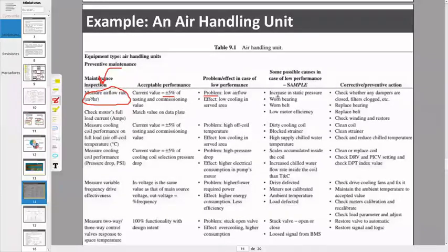Like an increase in static pressure. In that case, we still did not do any preventive maintenance, but we know from this problem and measurement that it could be an increase in static pressure. To fix that problem, we check the dampers, the filters, maybe the coil itself is blocked, and so on. So what we try to do is share everything that needs to be done for all kinds of equipment within the building, around 40 or 50 pieces of equipment.